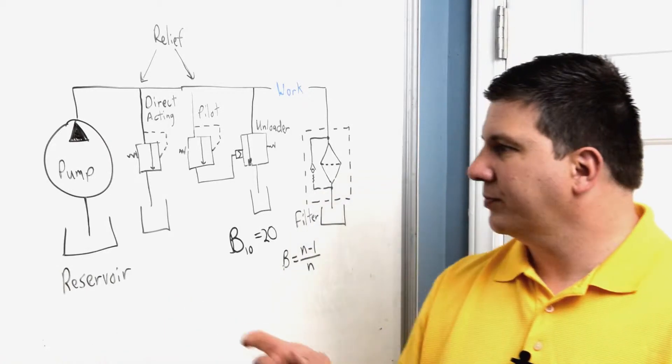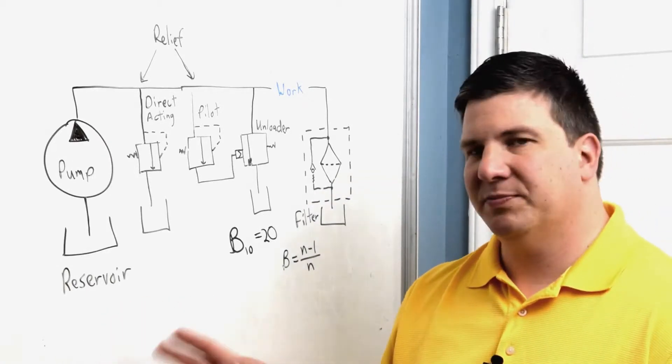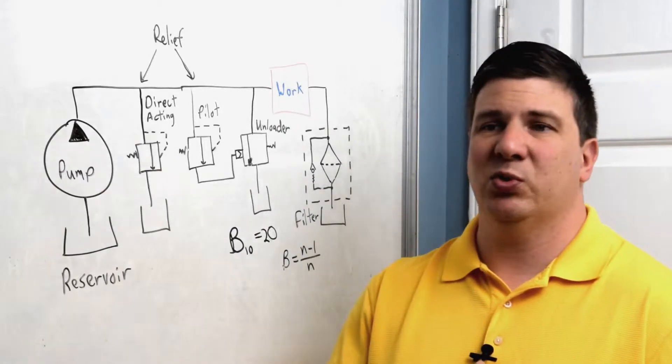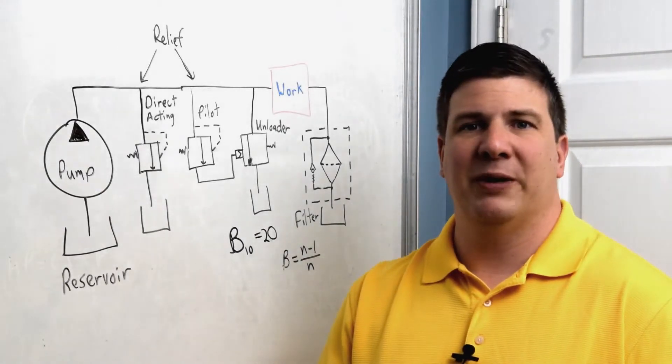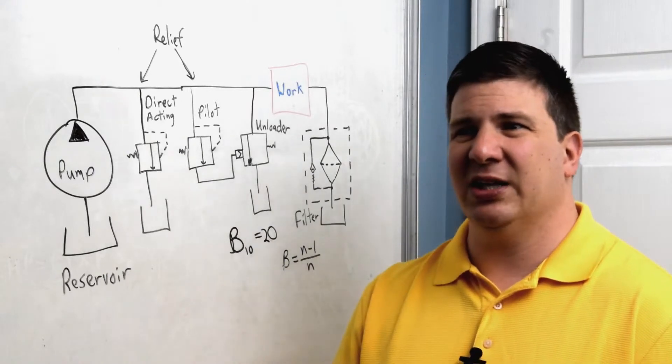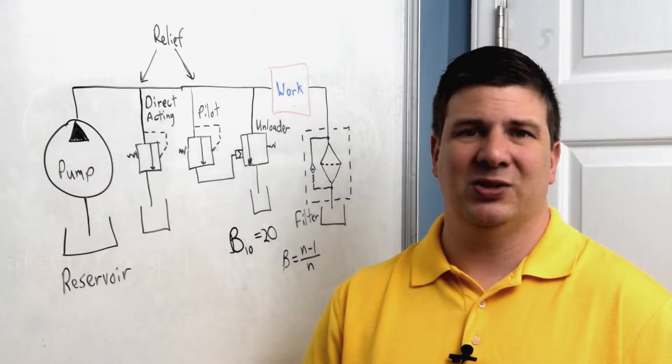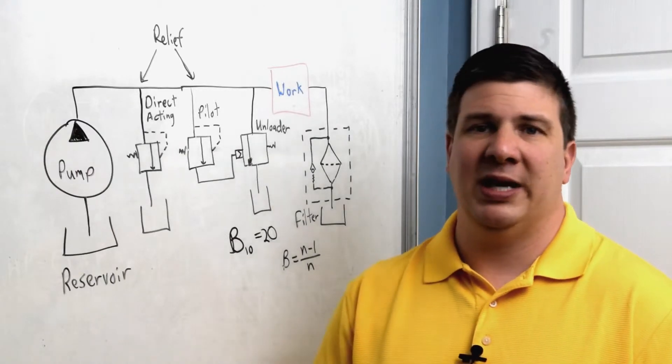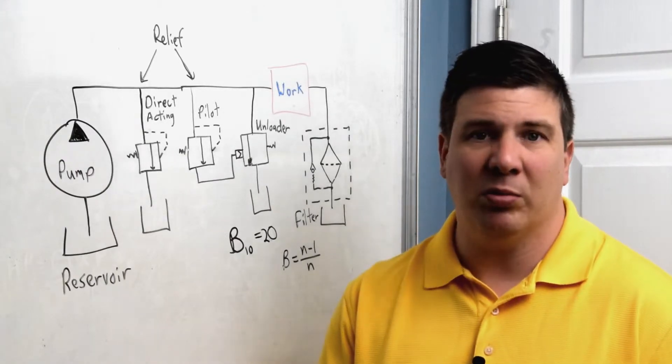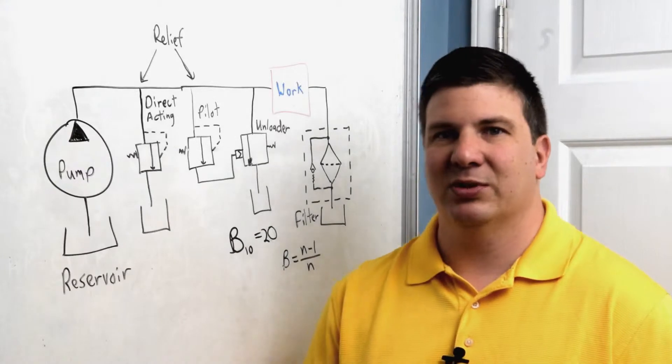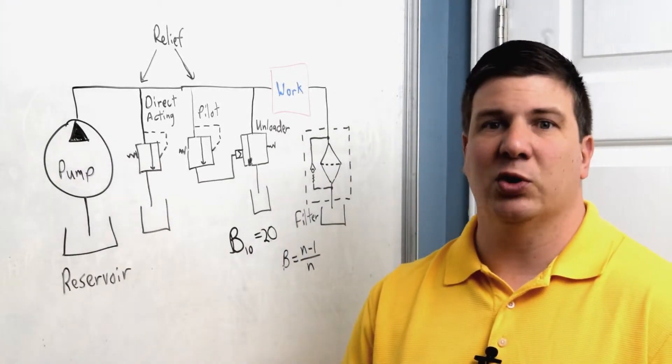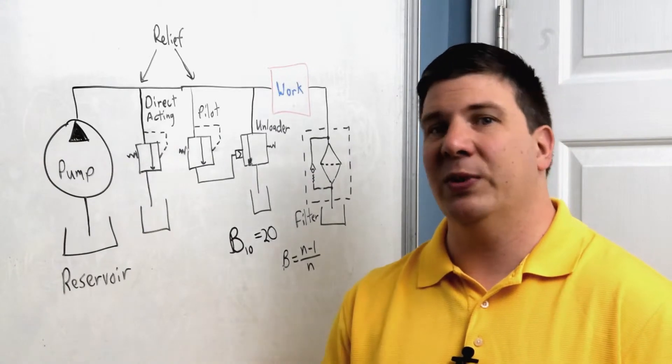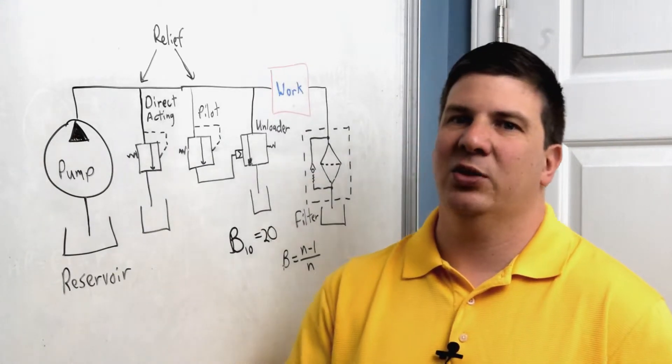At that point, there's other things to consider. As I mentioned, heat generation is one of them. But if I have a lot of heat generation, adding a lot more oil doesn't seem like a good idea to me. A better thing would be to add a heat exchanger if I have that problem. It's a lot simpler, cheaper. I can control my temperature and my fluid a lot better than trying to just add more oil and hope that's a big enough heat sink that it'll work.